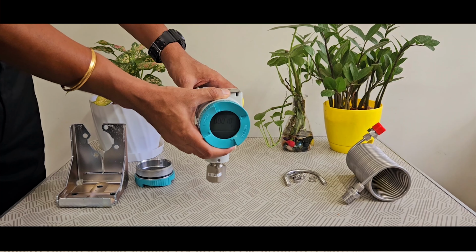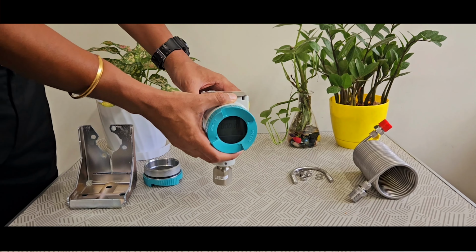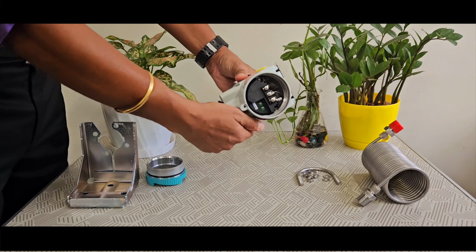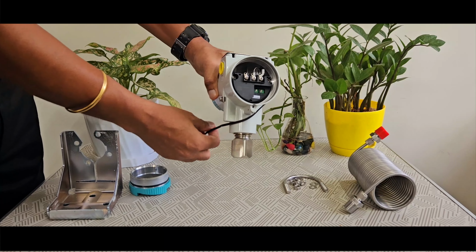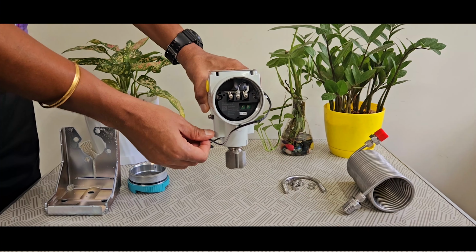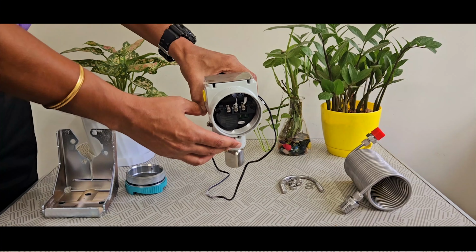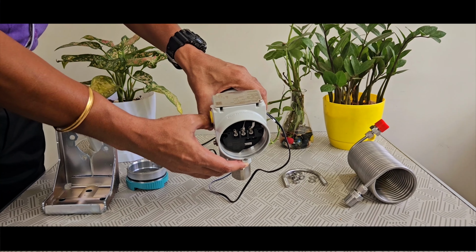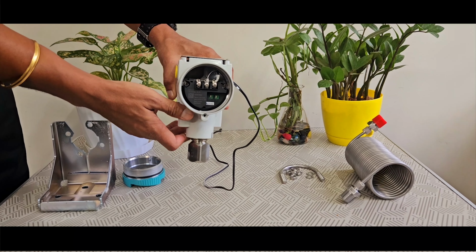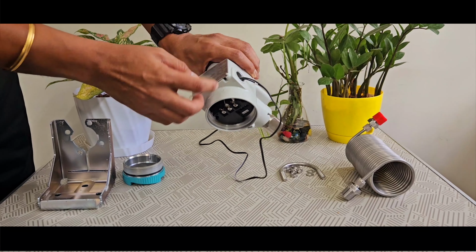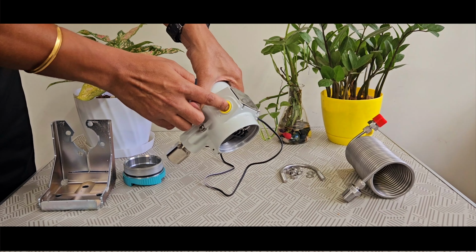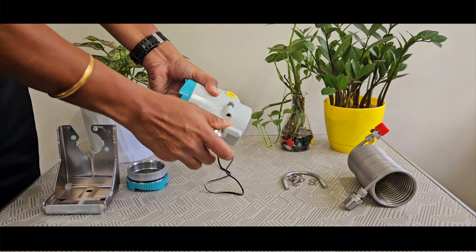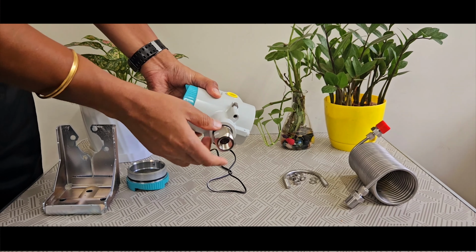However, without display we just have to use it as a transmitter which can transmit the data, and the acquisition system takes care. You can see the connection option. So I have taken a 24 volts DC to excite this device. However, it can be excited from 10 to 42 volts DC. At the side you can see the glands, and at the bottom you see this to put into the line pressure.